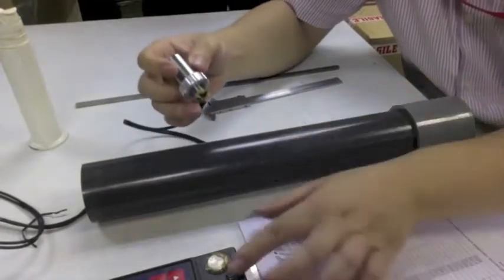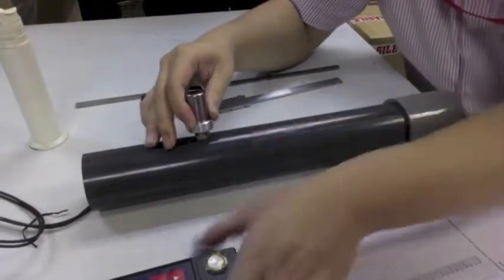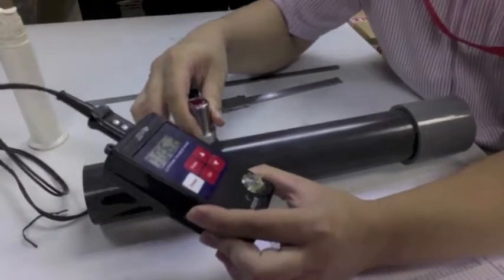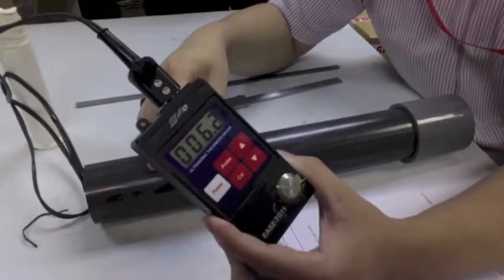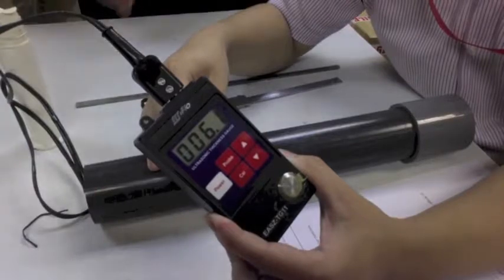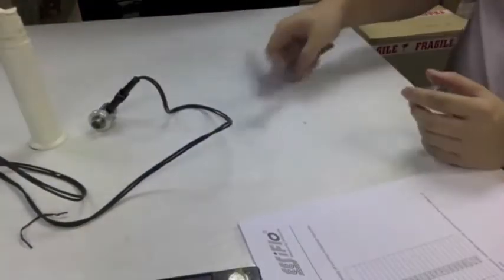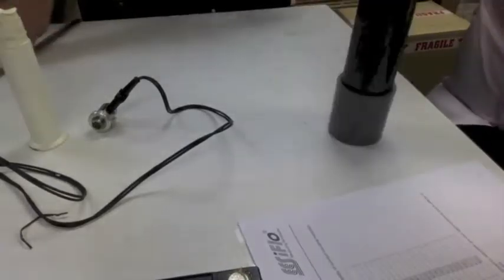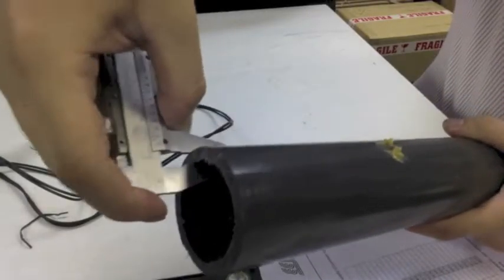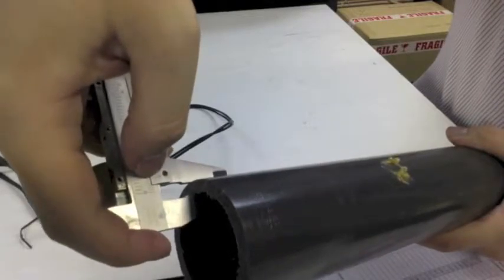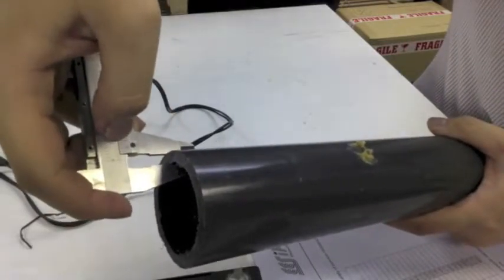Now you can take a piece of PVC plate or a PVC pipe and simply conduct the wall thickness measurement by applying couplant gel to the surface of the pipe. Make sure that you put the probe on level to the best level part of the PVC and hold it down. You'll see we have a measurement now of 6.2 millimeters. Initially, you may want to actually check the wall thickness of this PVC pipe using a vernier caliper, just so that you are sure that you're confident in taking measurements. This obviously won't be necessary when you're familiar with using the TG11 on a regular basis.